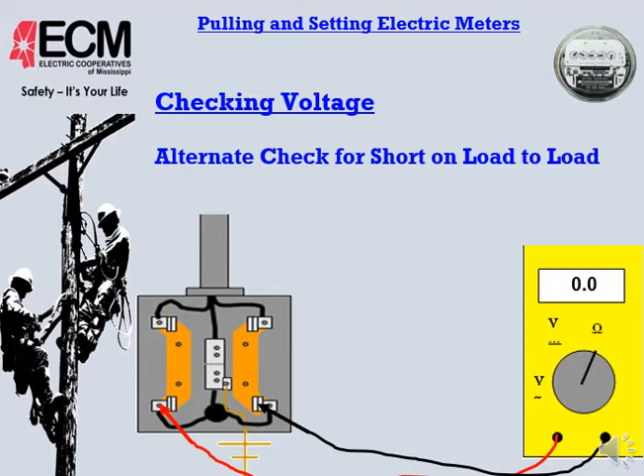A little bit of confusion here that I've noticed since I've been doing this program. I've noticed that a lot of people are confused when they put their meter in ohms and they get zeros like you see here. They think it's the green light, everything's good to go. But it's just the opposite. If you get a tone or you get zeros, that means that the conductor is tied together or it is the same conductor. Anytime you get a reading or you do not get a tone in the ohms position, then that means you're in good shape.